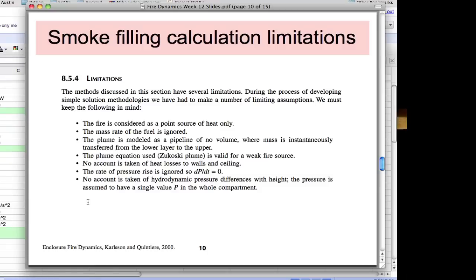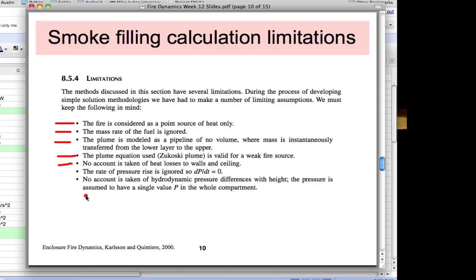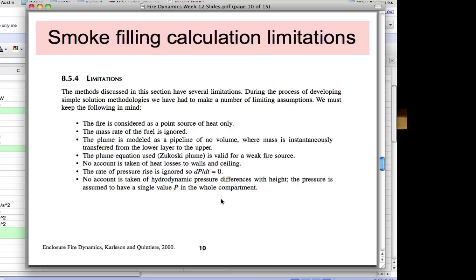This is a quick method to estimate, based on heat release rate and room dimensions, the time for the smoke layer to reach a given height — useful for evacuation or design criteria. However, there are limitations: the fire is a point source only, the mass rate of fuel is ignored, the plume is modeled as a pipeline of no volume, mass is instantaneously transferred between layers, no heat transfer to walls or ceiling, the rate of pressure rise is ignored (constant pressure assumed), and no account is taken of pressure differences with height.